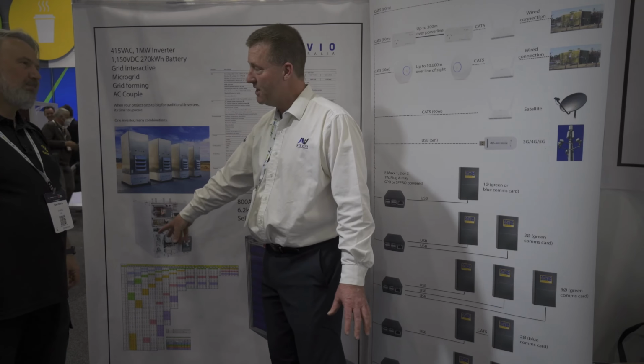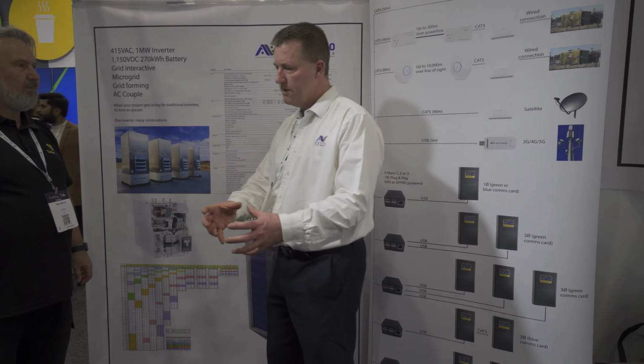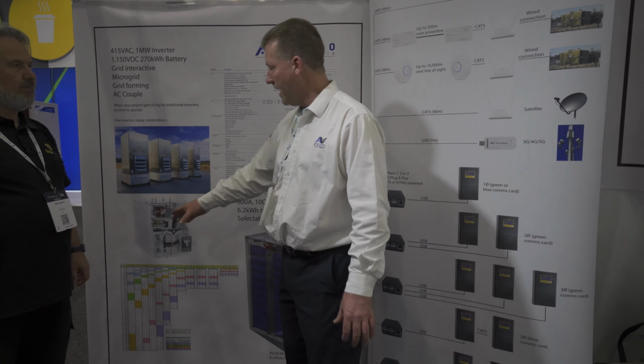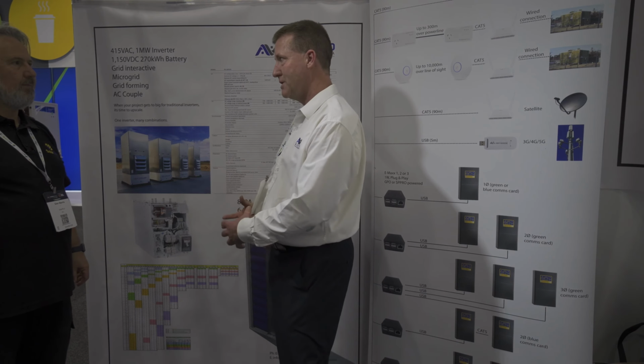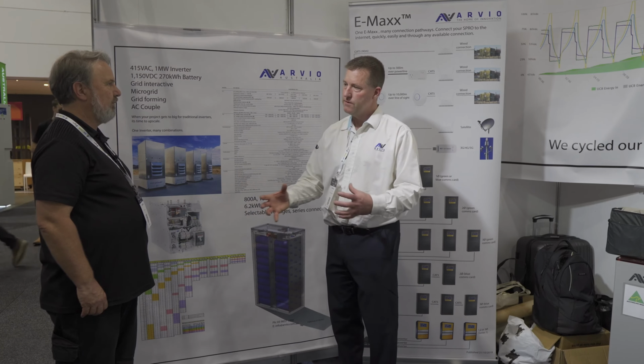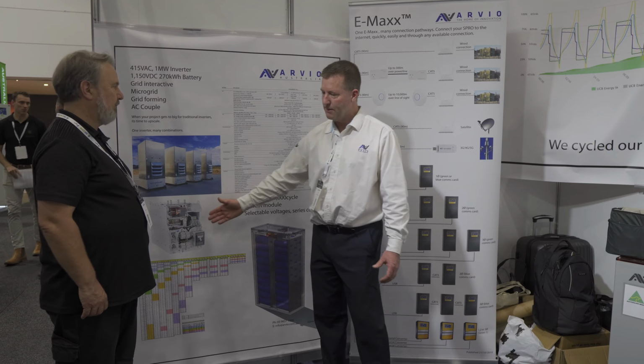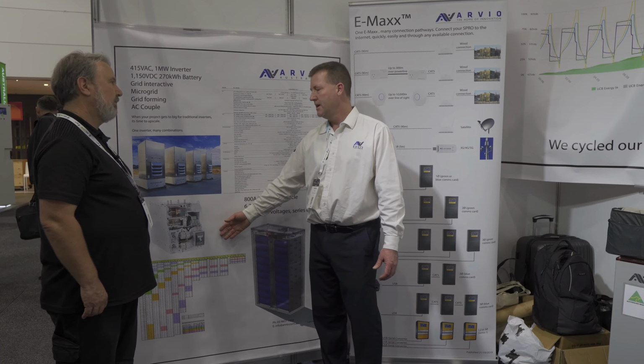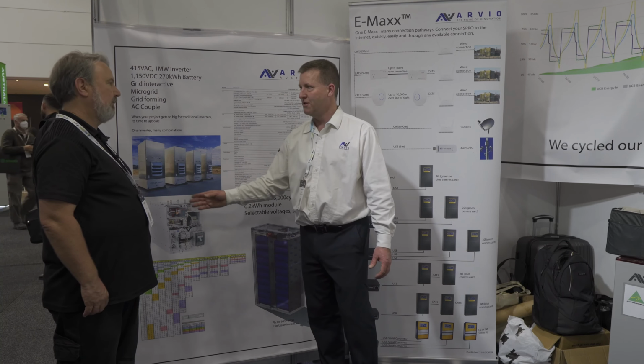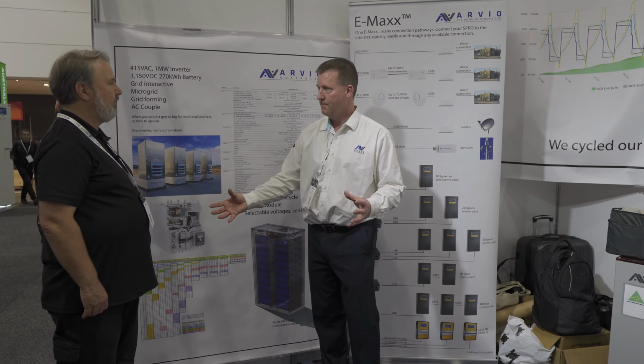Now, it does need an isolation transformer as well. Most inverters come with the electronics, inverter and transformer in the same box. In this case, they're separate, so you have to add a transformer, which takes up more space. But you can have different proportions, so you could put, say, a 3 megawatt transformer with a 1 megawatt solution on the inverter, and then grow the inverter side.